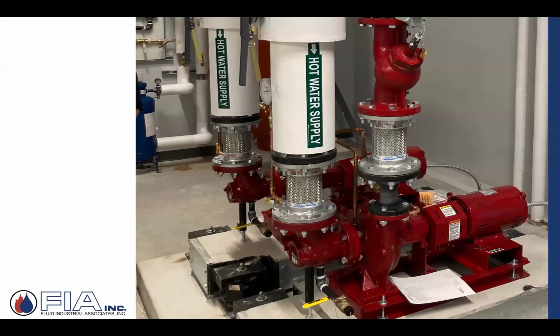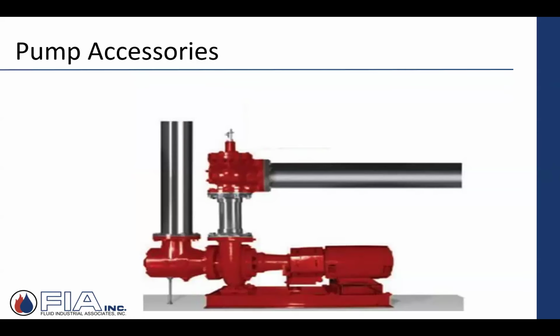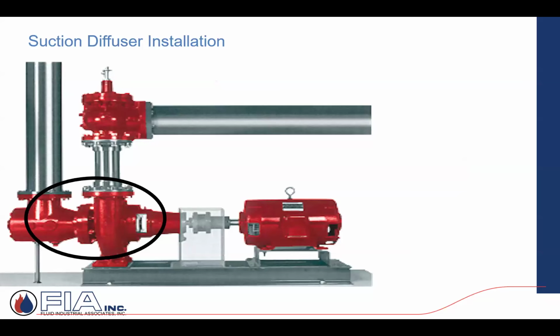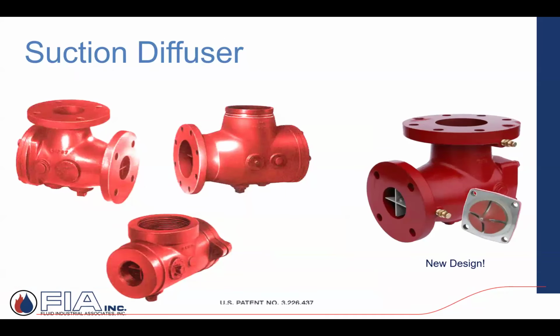From the field, here's a couple of pictures of one of those, or two of those pumps, if you will, with a bunch of the accessories that we'll touch on real quickly. But that's pretty common. That's a pretty standard type of pump you're going to see out in the field, this base mounted end suction. The accessories. So on the bottom left, that's kind of circled right here in the drawing or the slide, they're referring to a suction diffuser. So we'll just explain real quickly what that's all about. There's different styles, if you will, flanged connections. Some of the smaller ones might even be threaded, or maybe some type of Victaulic connection, depending upon the application.